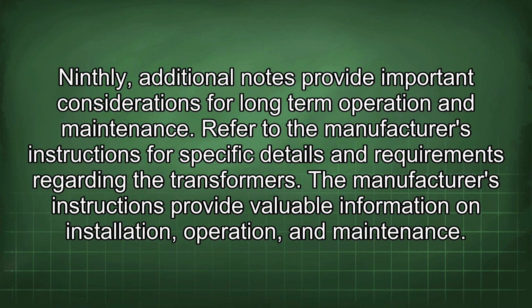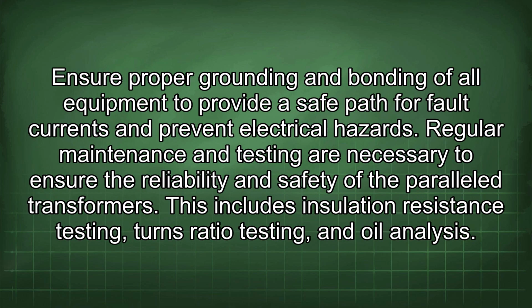Ninthly, additional notes provide important considerations for long-term operation and maintenance. Refer to the manufacturer's instructions for specific details and requirements regarding the transformers. The manufacturer's instructions provide valuable information on installation, operation, and maintenance. Ensure proper grounding and bonding of all equipment to provide a safe path for fault currents and prevent electrical hazards. Regular maintenance and testing are necessary to ensure the reliability and safety of the parallel transformers. This includes insulation resistance testing, turns ratio testing, and oil analysis.